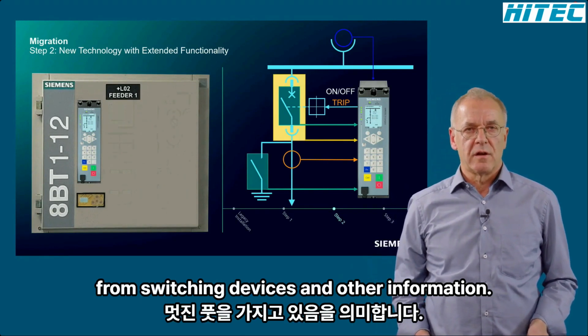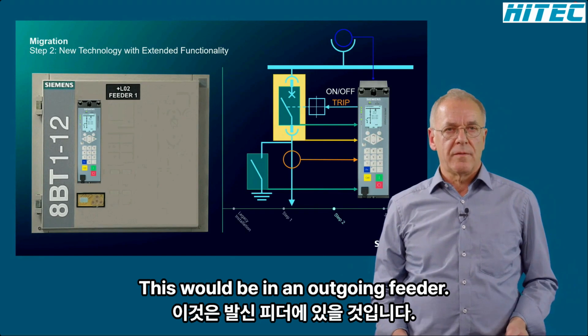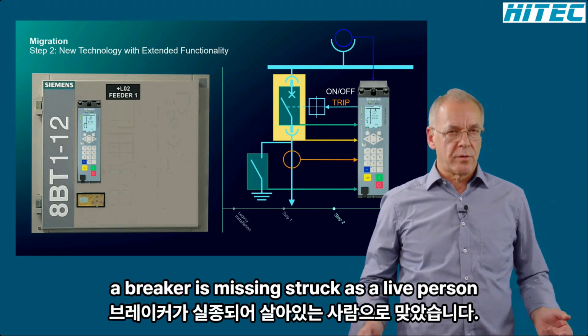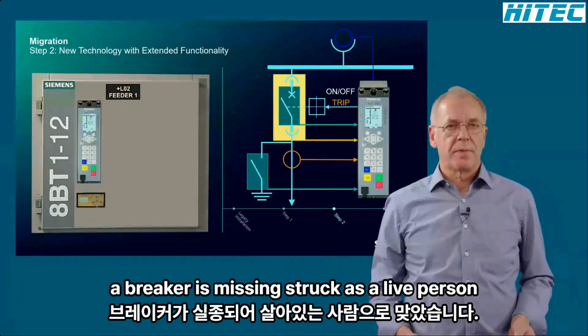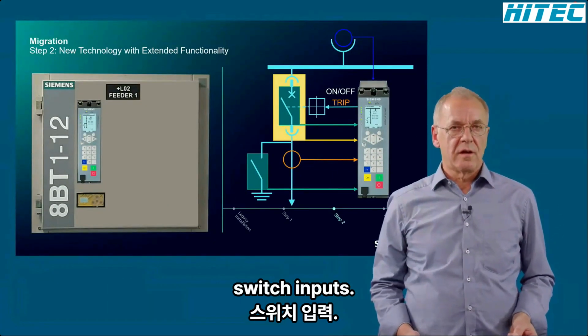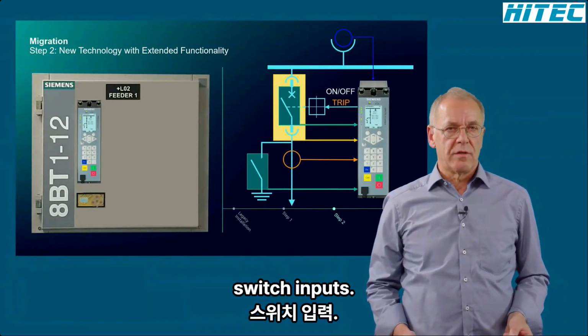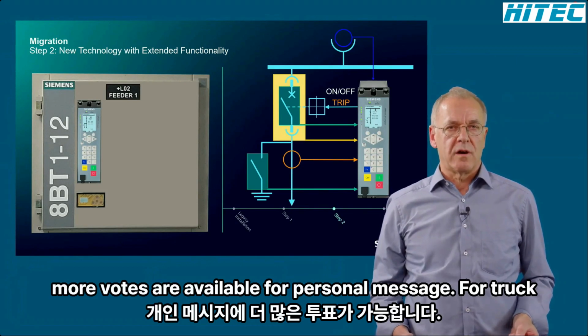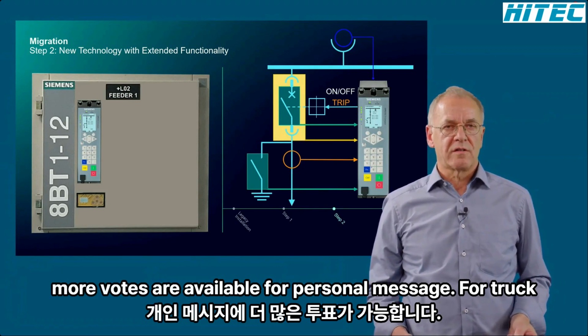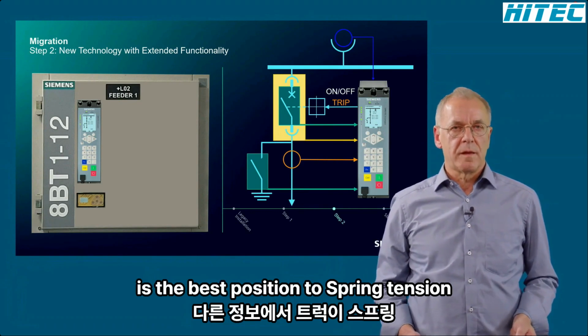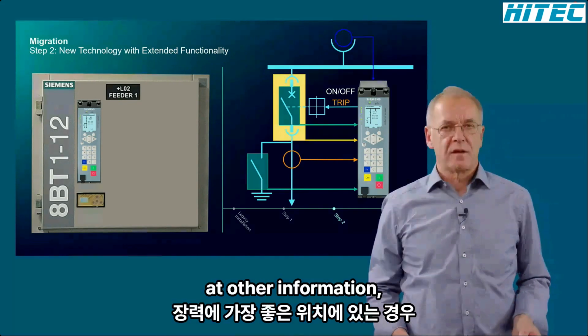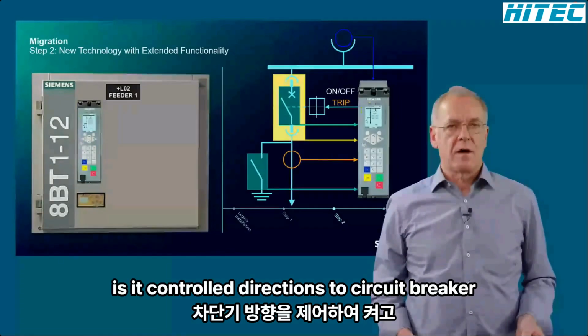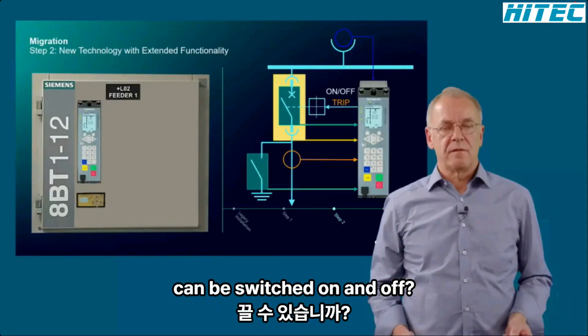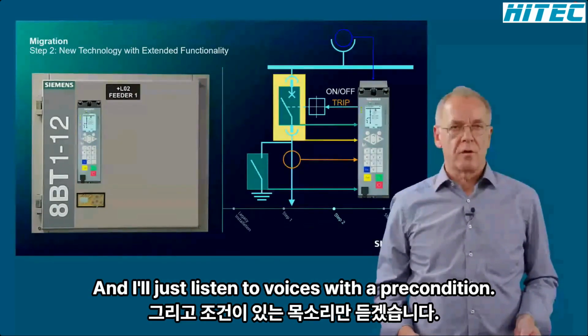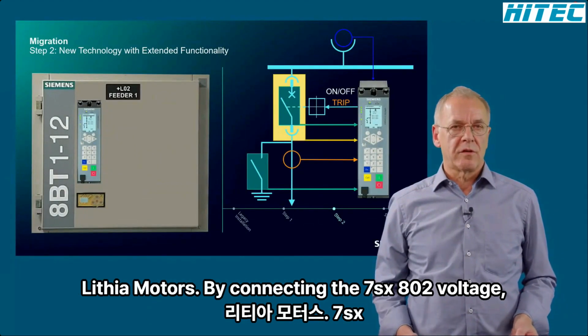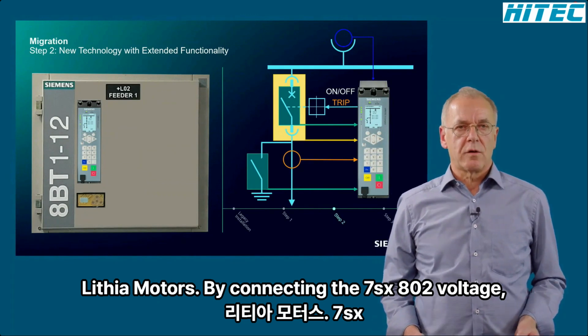and other information. This would be, in an outgoing feeder, the feedback from the circuit breaker, the switching truck, and the line earthing switch. These each require 2 binary inputs. Therefore, 8 more binary inputs are available for additional messages, for example, truck is in test position, motor spring tensioned, or other information. In the control direction, the circuit breaker can be switched on and off, and other switching devices too, with the precondition that they are motor driven.